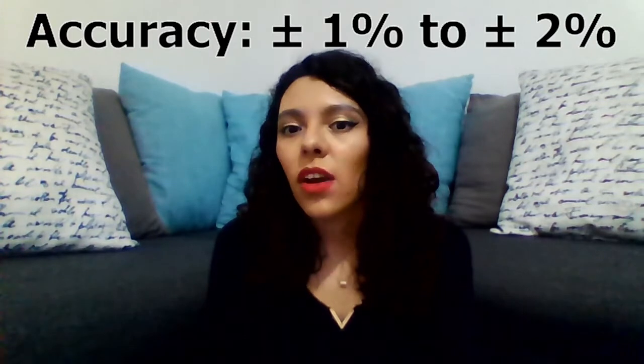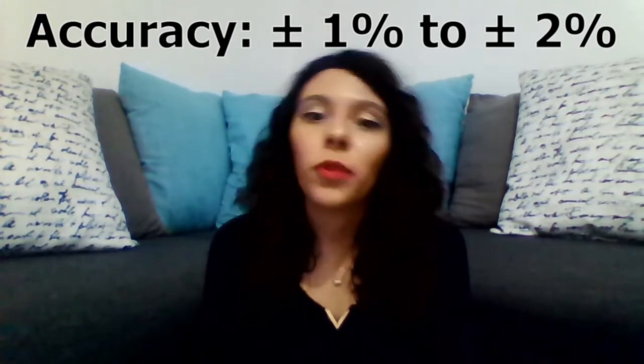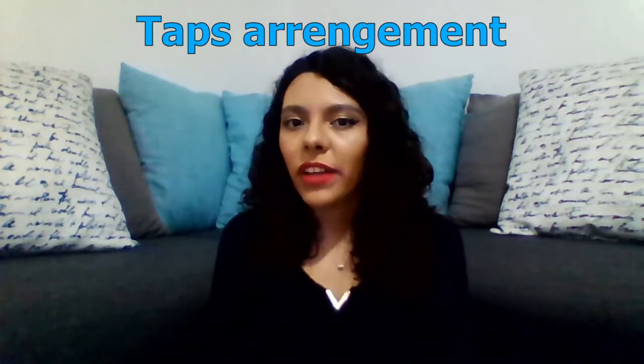The orifice plate or diaphragm is a perforated plate that is installed inside the pipe, having an accuracy of ±1% to ±2%. Those in charge of capturing the differential pressure are two taps. One goes before the plate and the other goes after the plate. Differential pressure is proportional to the square of the flow. The taps can be arranged as follows.